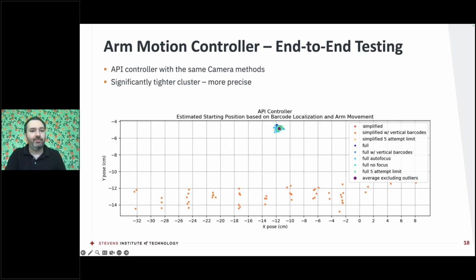So we moved on to a different controller, made available through the specific arm we were working with: the Kinova Gen 3 Arm's API for users of Kinova arm platforms. Using that controller, we were able to get the error down to a much more acceptable level. Again deploying the arm to make contact with desired measurement locations on a pothead compartment panel, we encountered much higher precision, and that 4 centimeter diameter circle of uncertainty shrank down to just a centimeter or two. So our ability to deploy the arm and have it make contact with the desired physical location now has high repeatability within about a centimeter or so.